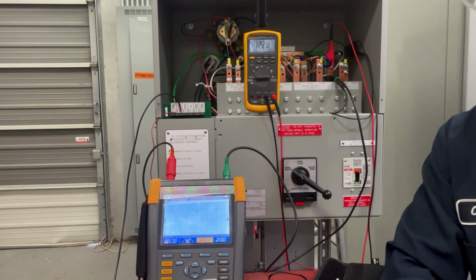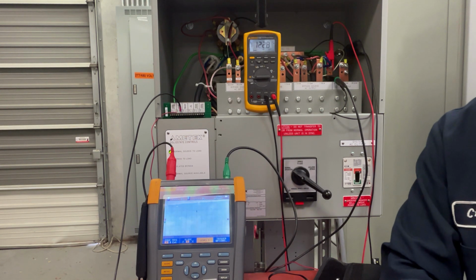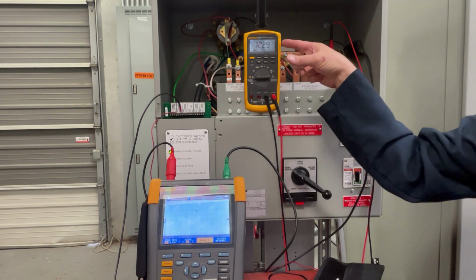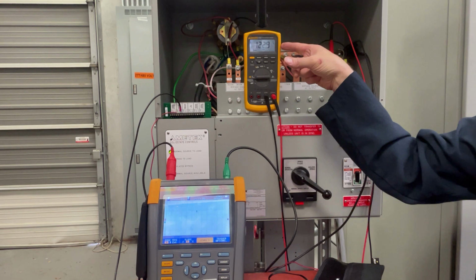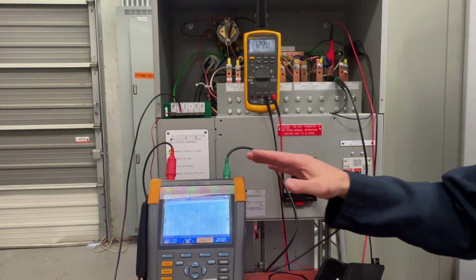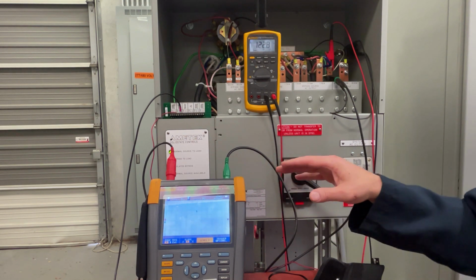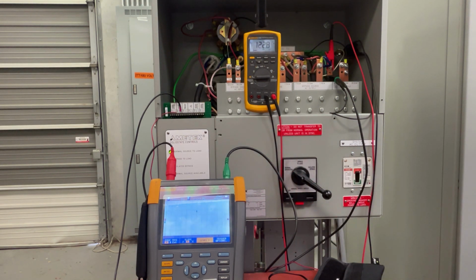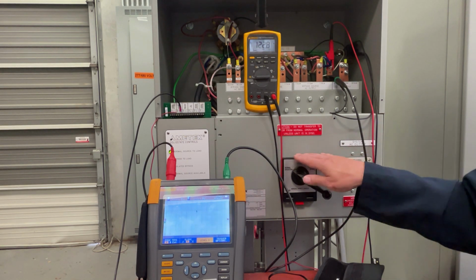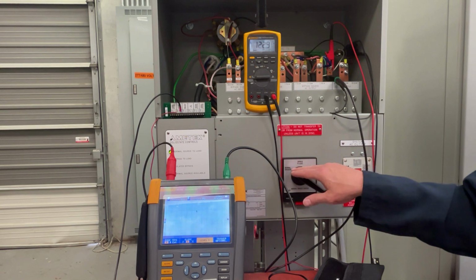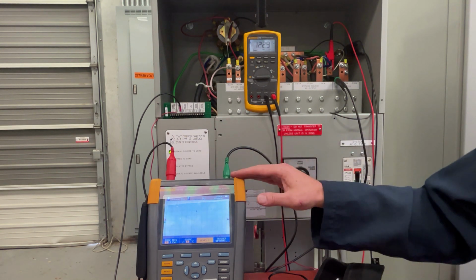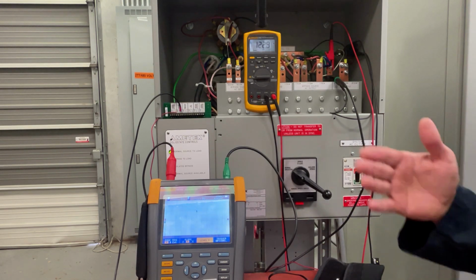Okay, so today we're going to show you a seamless transfer using an RMBS, a remote manual bypass switch, and we've got an oscilloscope and a Fluke 87 meter connected to the output terminals of the bypass switch. So these are the terminals that go to the load circuits. As you can see, the meter up here is showing you 122.9 volts.